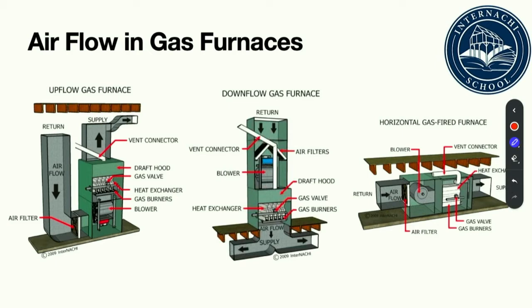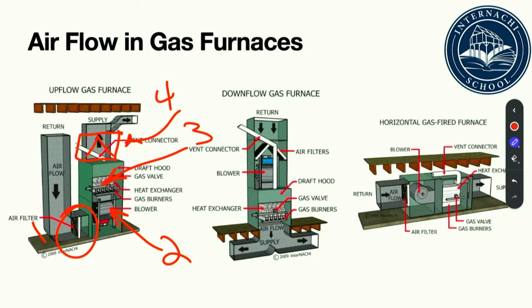So we're going to show a bunch of heat exchangers in a little bit. And I'm just going to do a little bit of an early primer, per se, on furnaces. So when we're dealing with gas forced air furnaces, the airflow and the order of airflow is what's important. Most furnaces are multi-directional, so it really doesn't matter if they're upflow, downflow, or horizontal. But what we do want to see is, number one, we want to go ahead and filter the air. And then number two, we want to send it through our blower. Number three is going to be our heat exchanger. And then if we did have an air conditioning coil, and these drawings do not, that would be last when we're dealing with the forced air furnace.